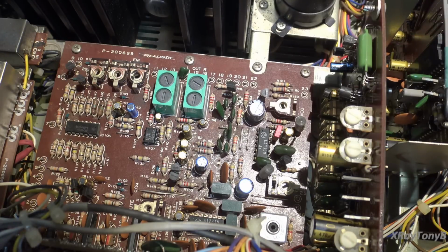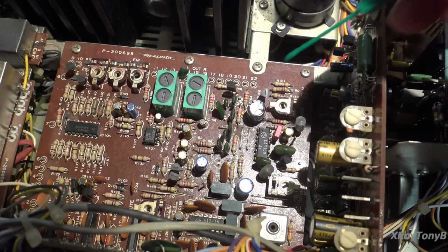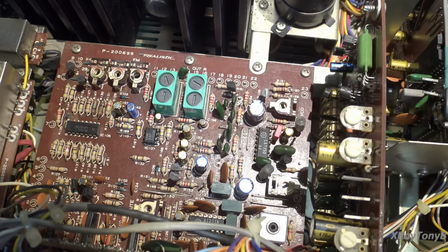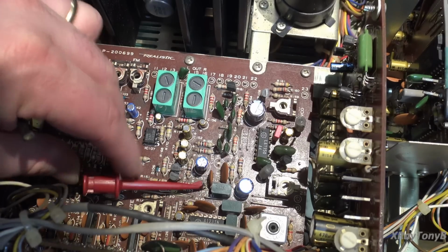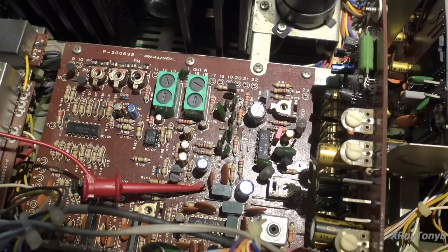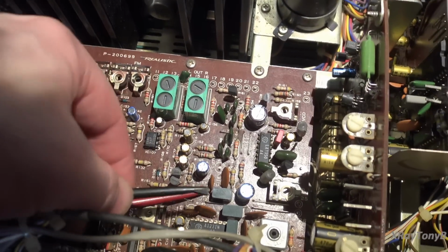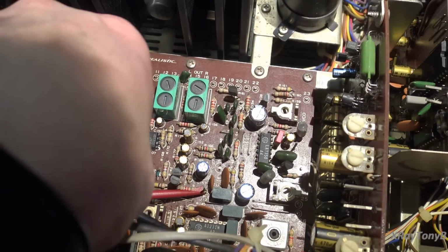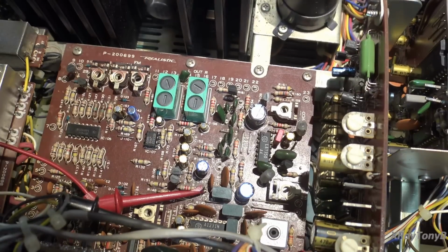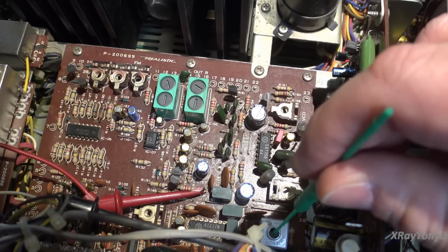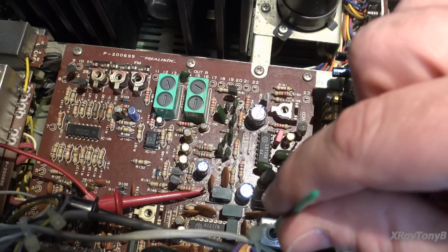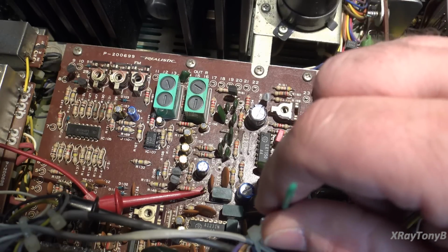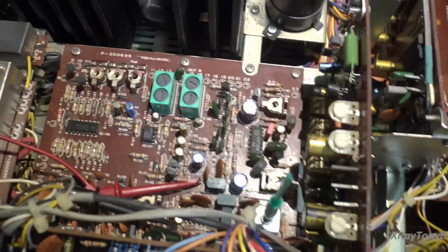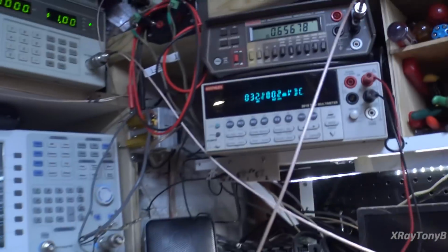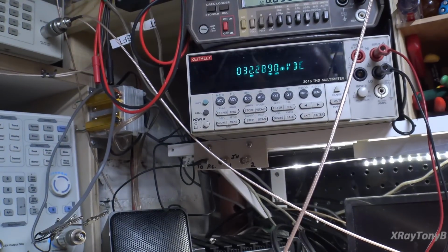And we want to connect our meter to 2 test points, which is TP2, we want our plus to be, and TP1, which is here, we want to adjust. Sorry, I'm hitting the camera because I'm working around the camera. And we want to measure our voltage. Here's the top of the coil. We want to go down through it and get into the bottom coil, and we want to adjust it for about 30 millivolts, is what the service manual is saying. So let's see if we can get 30 millivolts on here, because we're off a little bit, I see.